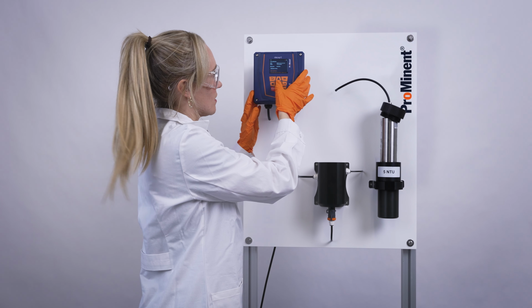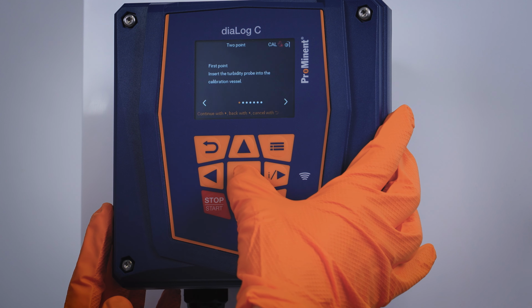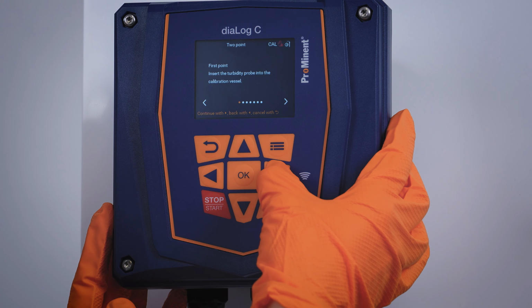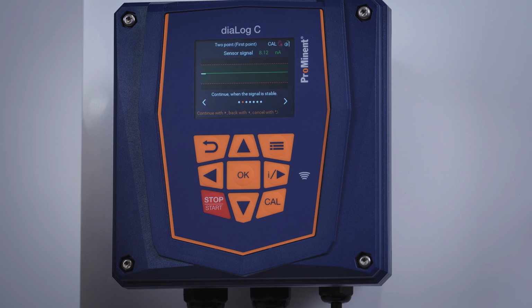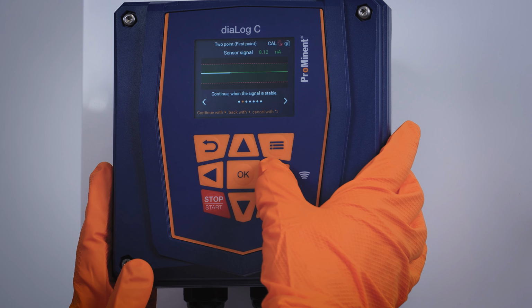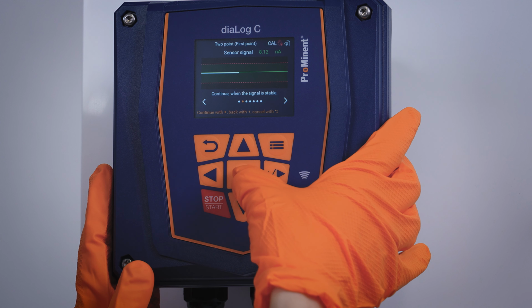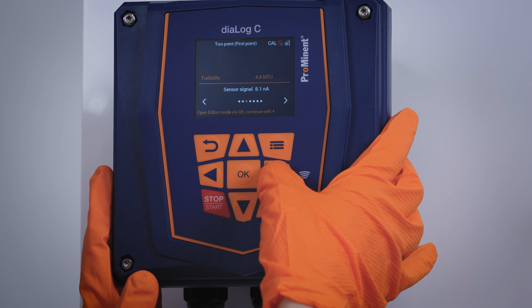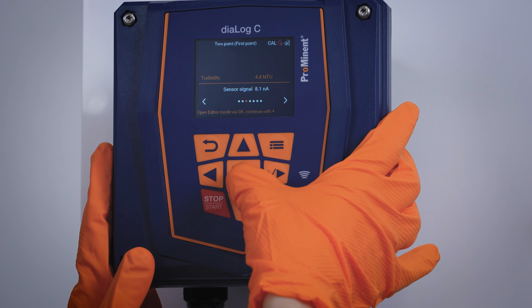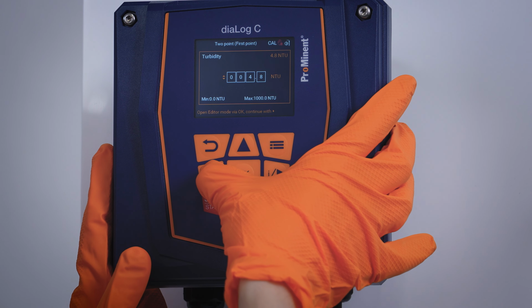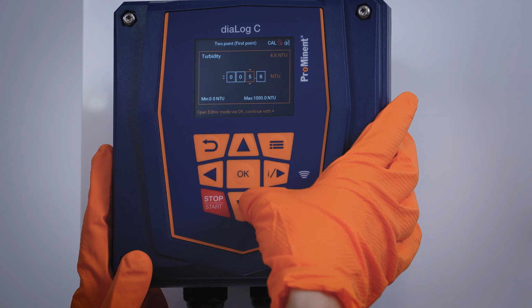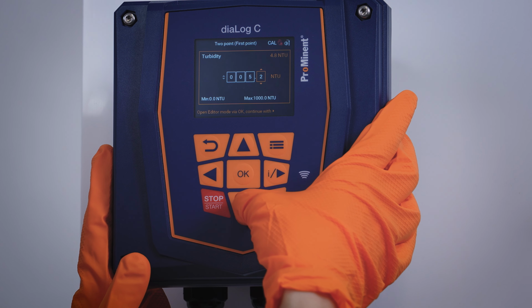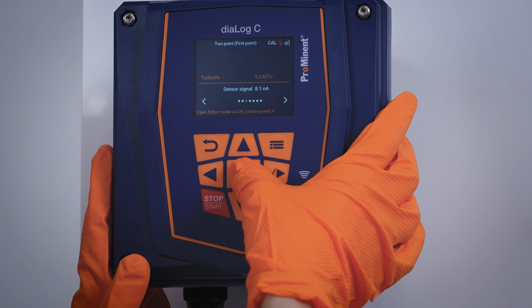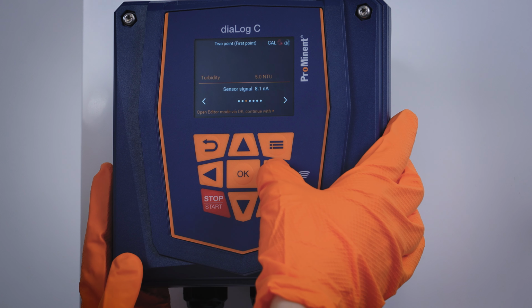In the controller, you start the calibration. And then you wait for the signal to become stable, which can take about, let's say, 20 seconds. And if the signal is stable, then you say next, and now you enter the turbidity value, which here is now 5 NTU. Enter. Then you go to the next step.